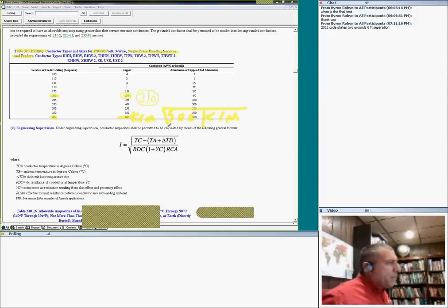If the same panel was to be installed in another dwelling, take advantage of this very interesting table for residential only. It gives you a smaller size, guys. It gives you smaller copper or aluminum sizes for service or feeders. And by the way, this is not just for the service. So my panel is a 400 amp panel here. This is my service, and from here, if you go to a 100 amp panel, it also is the feeders.